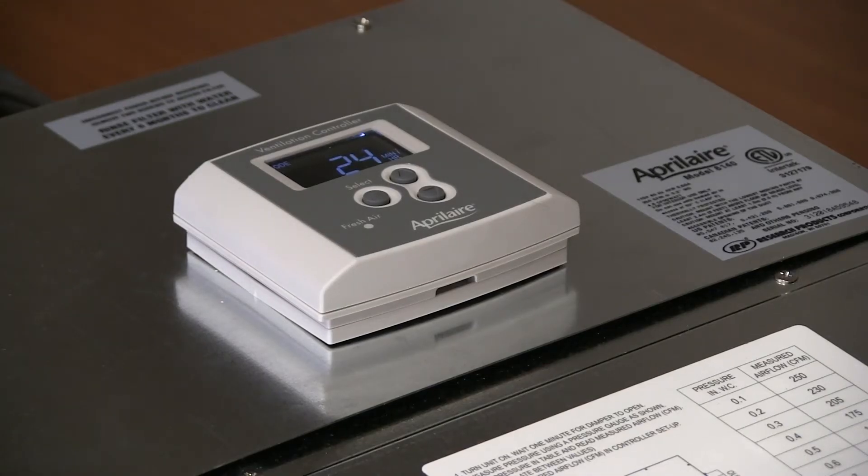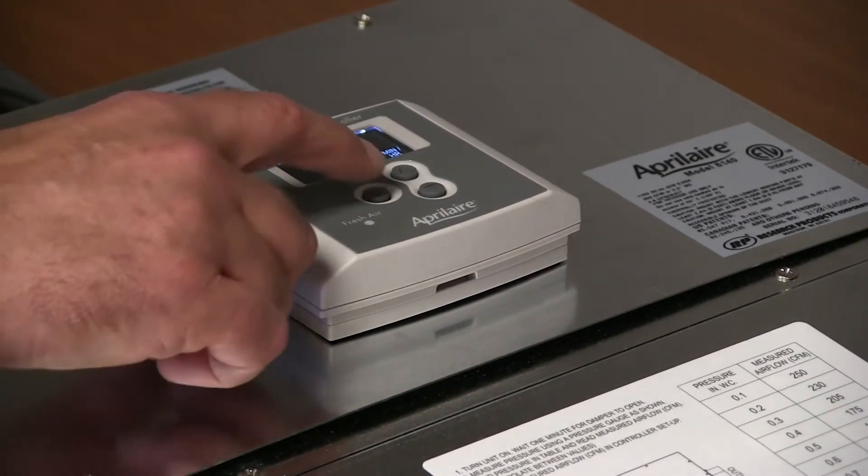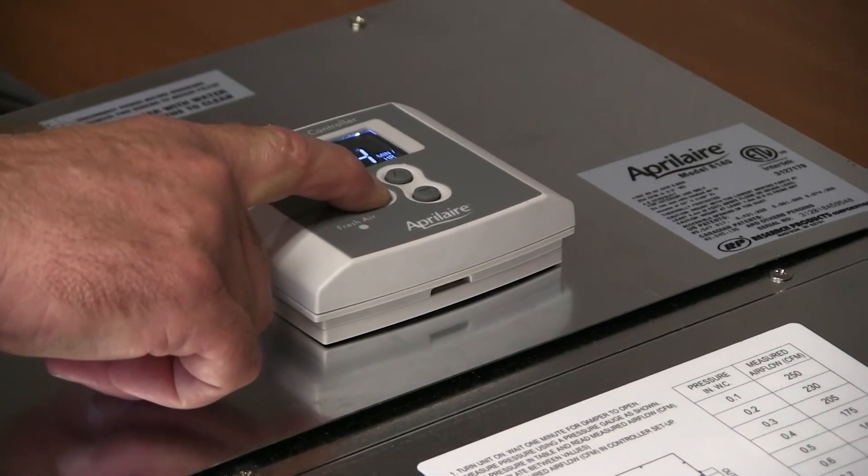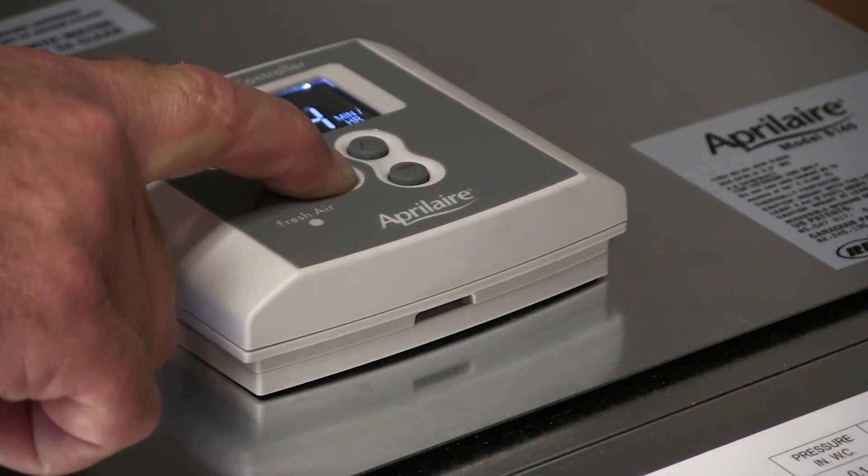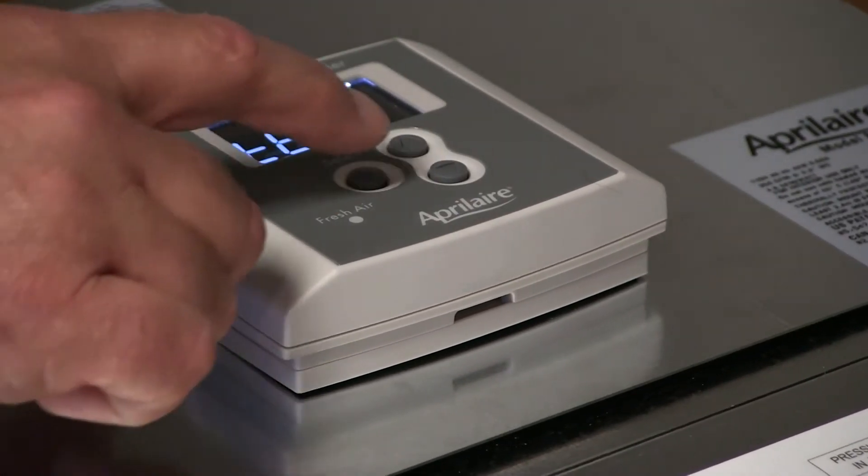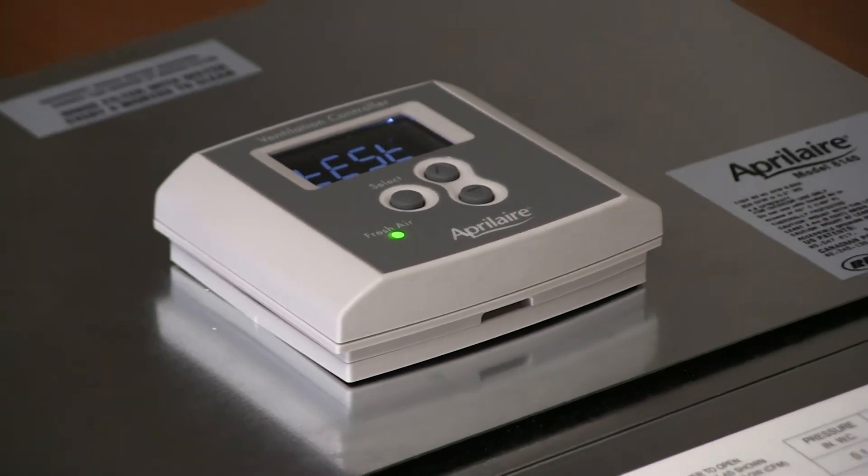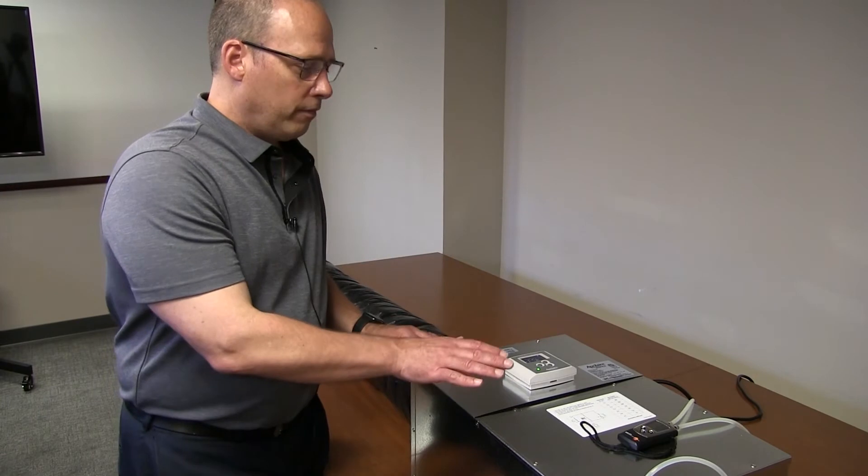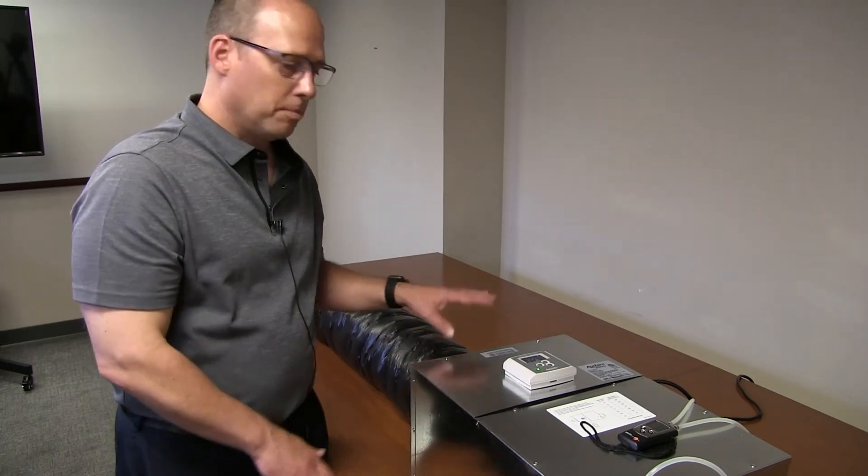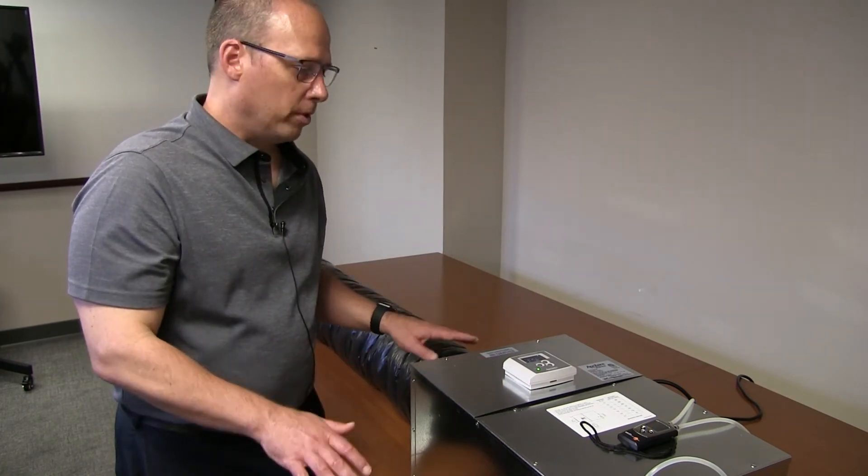So to test the unit, we've implemented a test procedure into the control of the 8140. To access that, we're just going to press and hold the select button, and that will give us two options, either setup or test. We toggle between those options using either the up or the down button. So we'll select test, and what that will do is it will start the fan. After the fan starts, you want to give the 8140 about 45 seconds, because there is a built-in damper into the 8140. That takes about 45 seconds at most to open.